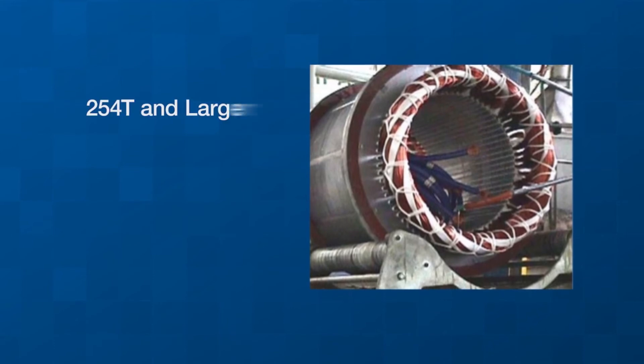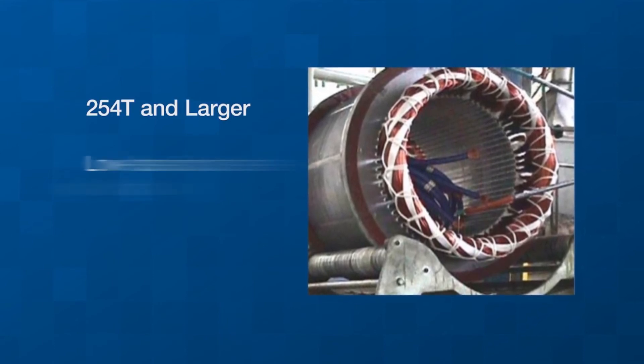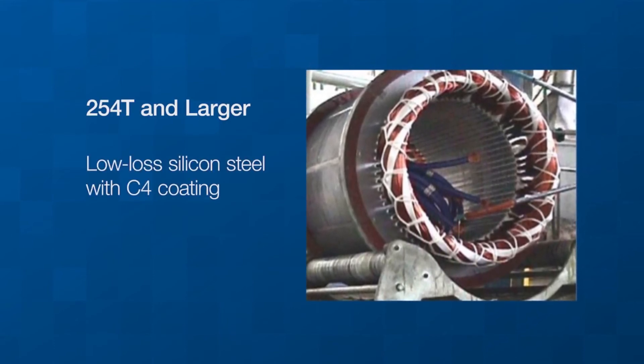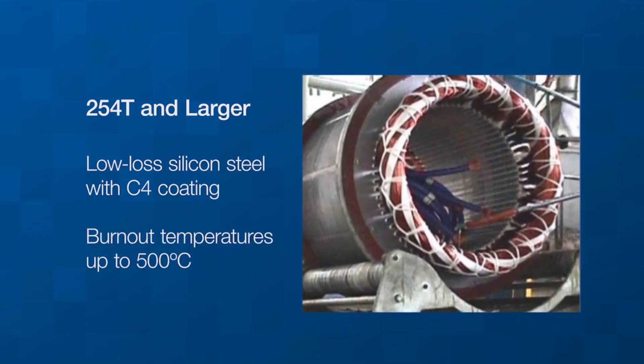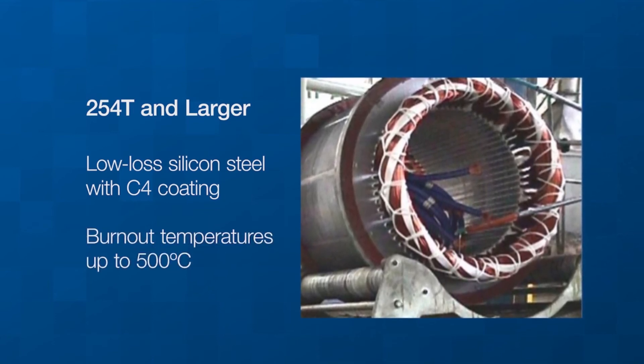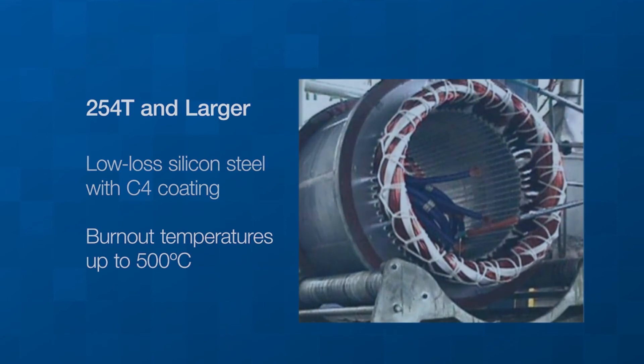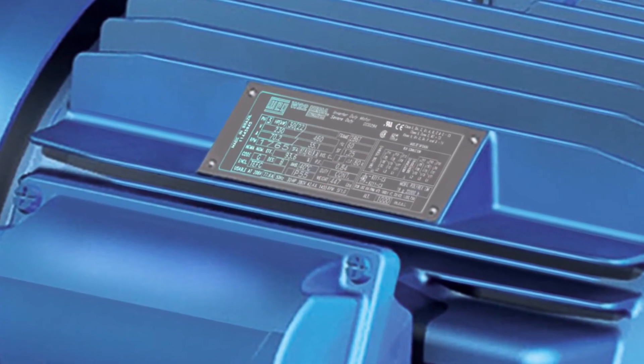Stator core steel on frames 254T and above use low-loss silicon steel with C4 coating, which allows for burnout temperatures up to 500 degrees Celsius without efficiency impact during a rewind. A drain plug, positioned at the lowest level, allows condensed water to drain from the motor. The stainless steel nameplate includes Division 2 and VFD data along with lubrication intervals.